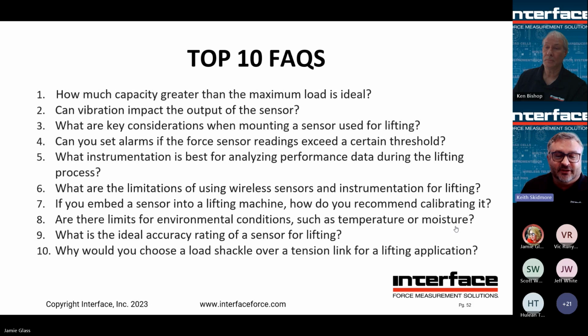instrument. What are the limitations of using wireless sensors and instrumentation for lifting? Certainly line of sight and distance. They can transmit up to 500 or 600 meters line of sight. If you don't have line of sight, it drops dramatically. You can potentially transmit from one building to another. It may or may not work. A site survey can tell you that. If it doesn't, remote antennas and repeaters can be added to a system. But definitely there's also a limitation of data rate. If you want very high data speeds and a lot of load points, wireless may not be the answer. So definitely application specific.